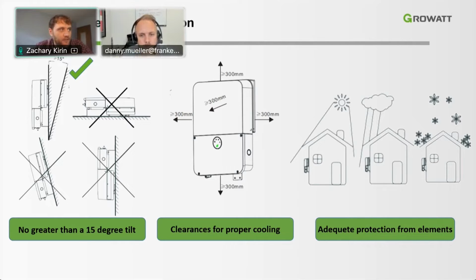So some adequate protection from the elements is definitely necessary for the system as well. We don't permit the inverter to be installed in direct sunlight. We also recommend the inverter be placed in a way to mitigate water intrusion, such as if the inverter was placed directly in front of the home on the south side. This is not good because the sun would be hitting it constantly, and it receives some extra wind, snowfall, and rain. So we want to be sure the inverter is adequately protected from these elements. I will say it has a NEMA 4X rating, so there really is no worry about installing the inverter outdoors, but we still want to give the inverter the best possible area to install.